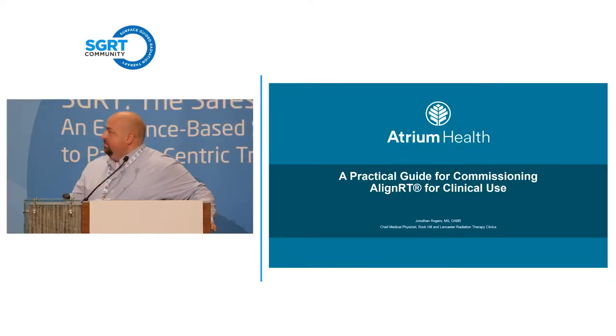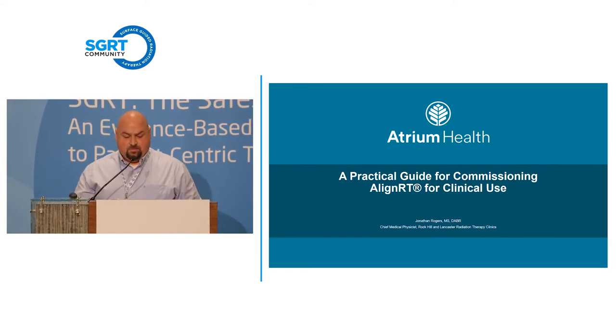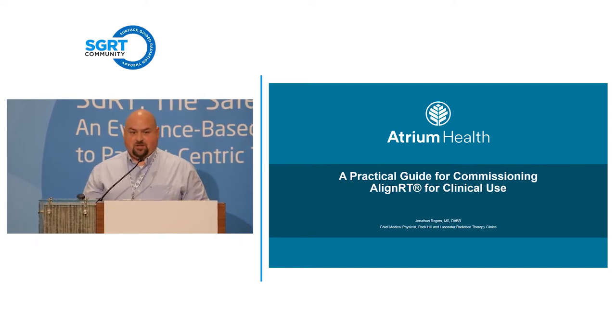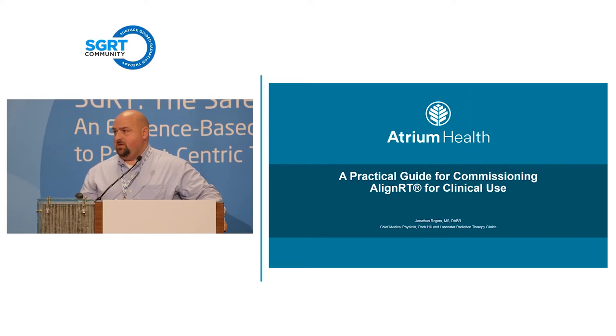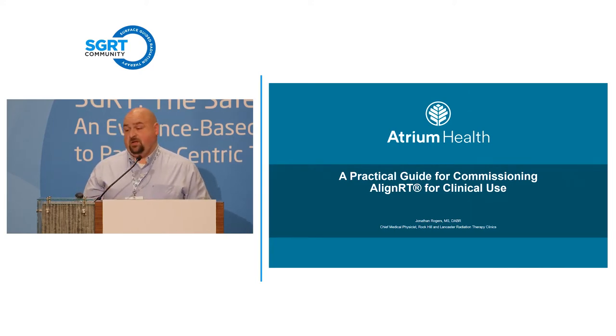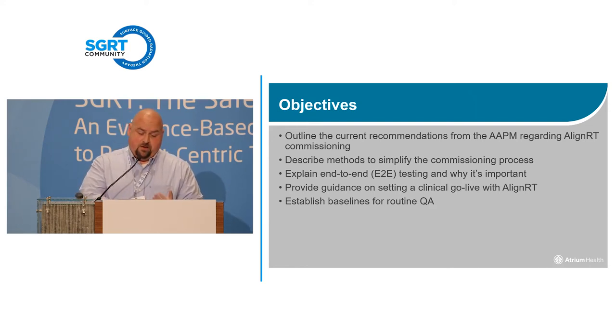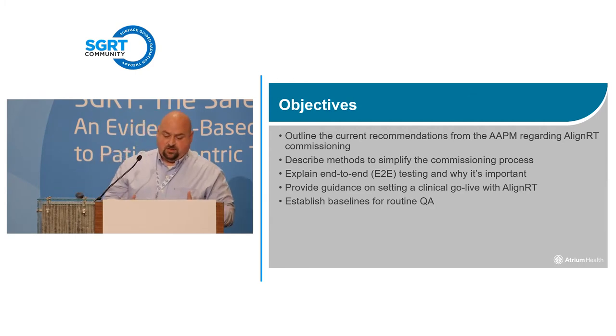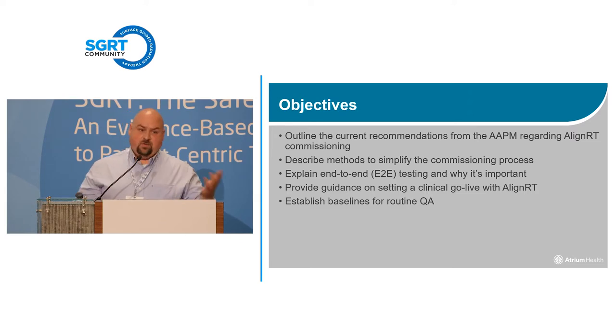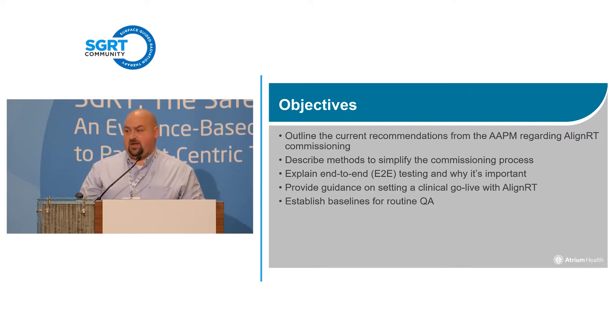We're talking about a practical way to commission a system. You can get into task groups and all that, but the best thing is to characterize your clinical use of the system — test things you're actually going to use clinically. That makes your testing a whole lot easier if you quantify it. We are going to go through the AAPM recommendations of what you should do, and this is going to be heavily guided by end-to-end testing.